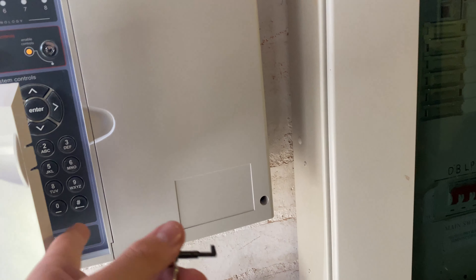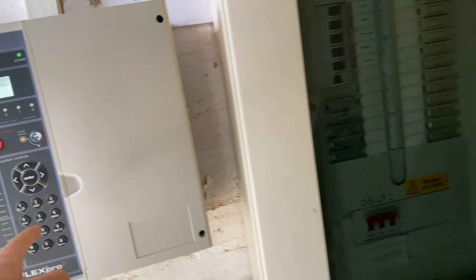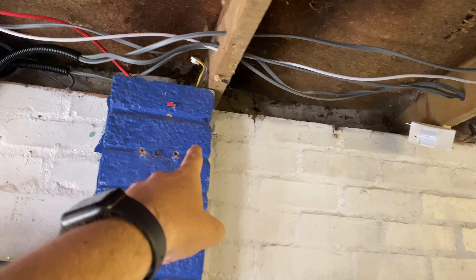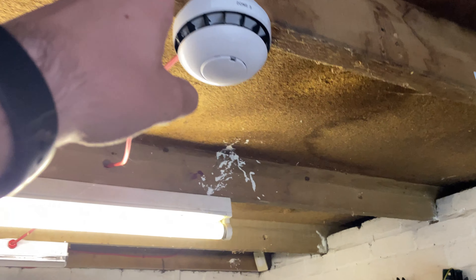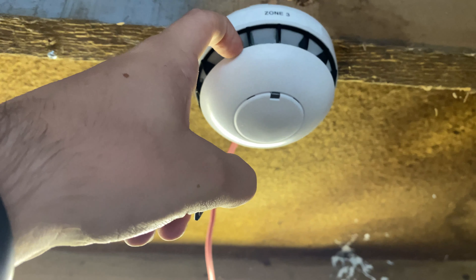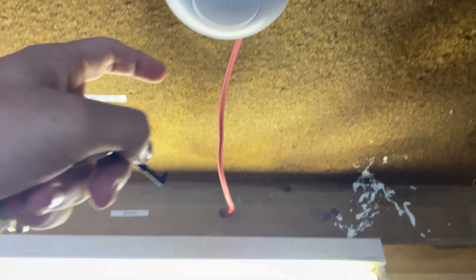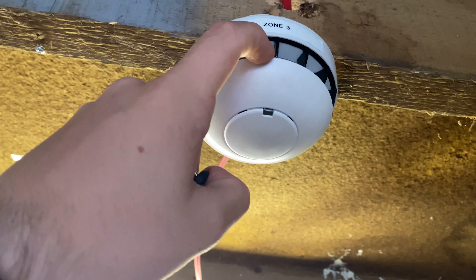This is just a quick update video on the Twin Flex Pro 2. We've got rid of the KAC sounders — I've left the cable there temporarily in case they have to go back up at any point. This detector was the one that killed all the other panels, but by putting it on zone three I've noticed it's fine. So we've got rid of all the KAC sounders and put all of these in now.